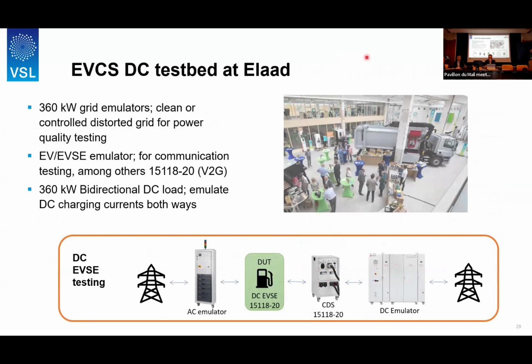I mentioned Elaad a few times now. Elaad is a facility in the Netherlands, constructed by the grid operators to focus on the EV charging systems and their influence on the electricity grid. What they can do here is test all kinds of charging stations in combination with real cars. You see here a truck, one of the biggest ones they have tested so far. They have 360 kilowatt grid emulators, so they can provide a very clean signal. And they can also do that for controlled distorted grid conditions and for power quality testing.